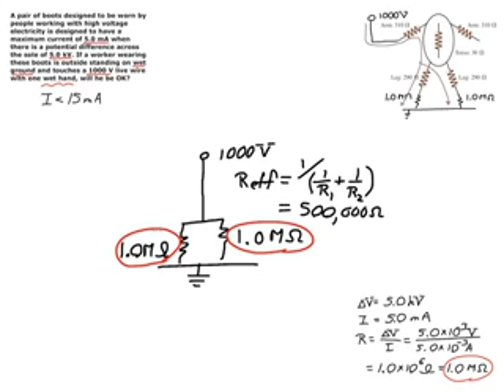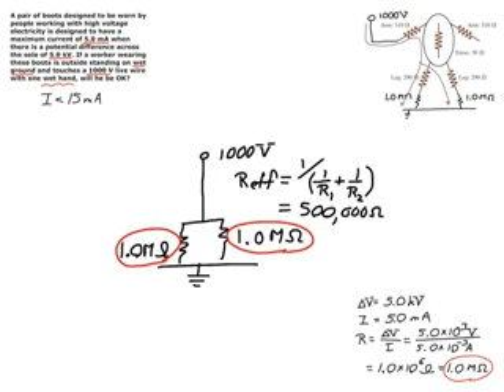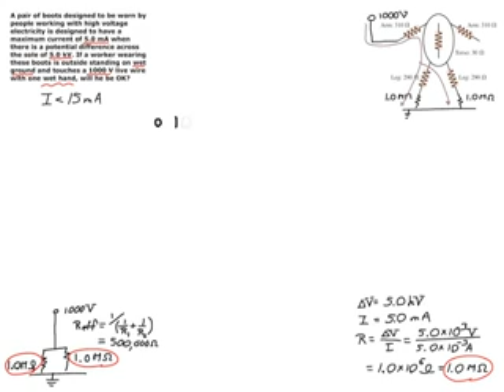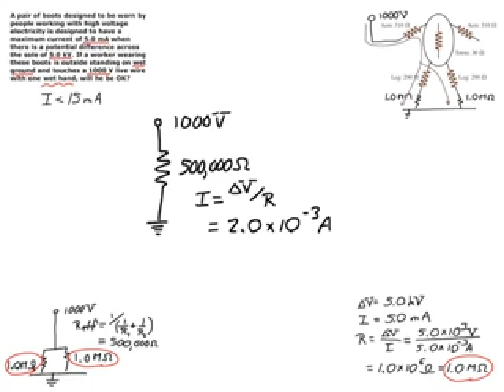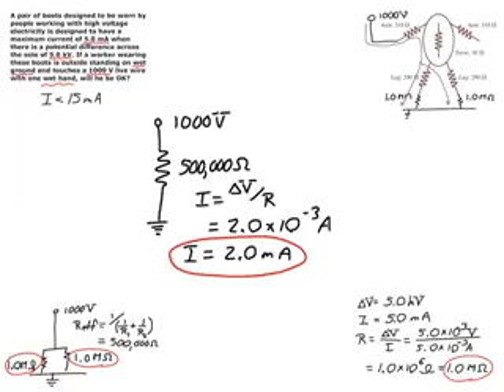That's a shortcut: if we have two resistors of the same value in parallel, the resistance is just half of either of them. So with that change, the circuit looks like this. I've got 1,000 volts, and between 1,000 volts and ground I have a single resistance. Everything considered together, the body plus the boots, has a total resistance of 500,000 ohms. So the current equals the potential difference divided by the resistance, 1,000 volts divided by 500,000 ohms, giving a current of 2.0 times 10 to the minus third amps, or 2.0 milliamps. That's less than the threshold to cause any injury, which is good.